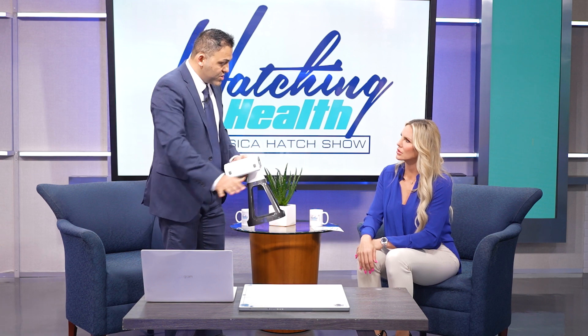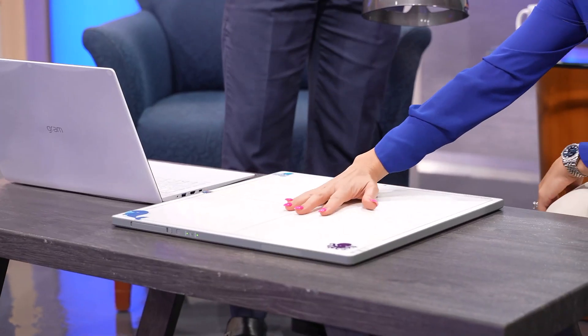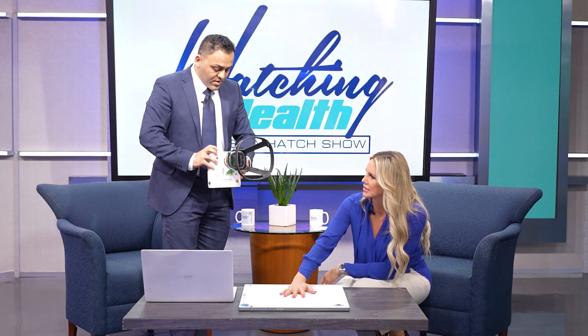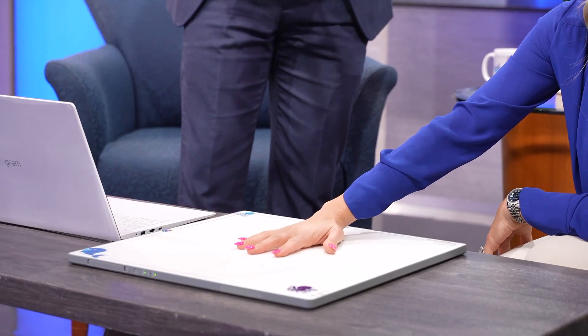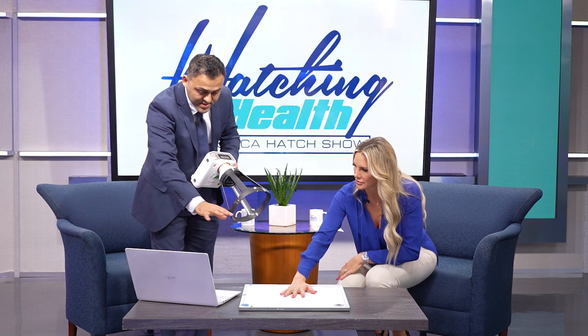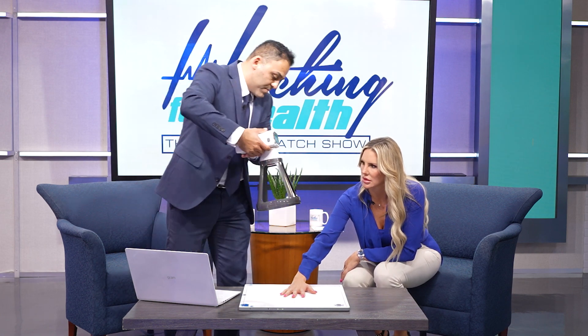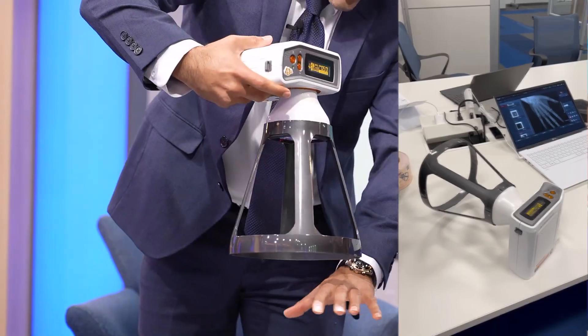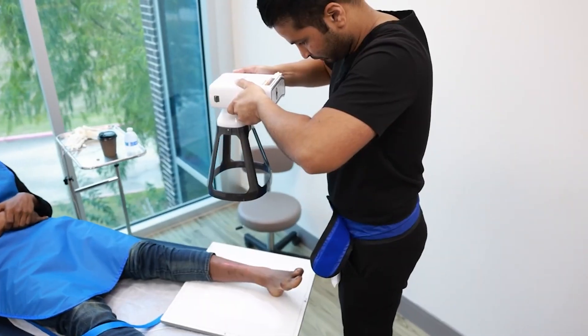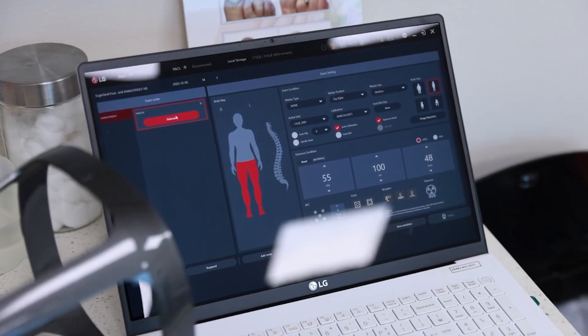For a demonstration of how a hand x-ray might work: there are three buttons on the device—one here, one here, one here. You press them and in less than three minutes the system boots up. The laptop is on and showing the environment where the x-ray will appear. An icon confirms all connectivity is maintained and the system is ready for imaging. When you press the button, the collimation area lights up, indicating the area that will be exposed to x-ray. You hold the button for three seconds, it shoots the x-ray, and the image is compiled on the software and appears immediately on the laptop.